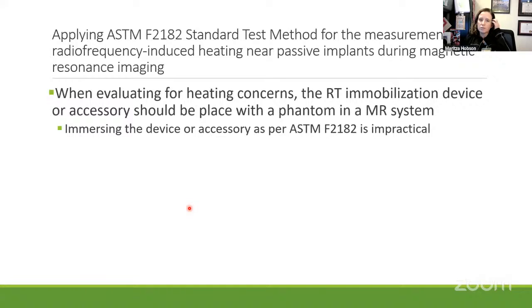Okay, so when we're applying ASTM F2182 for evaluating the heating concerns, the RT immobilization device or accessory should be placed with a phantom in an MR system. So why do we recommend a phantom? This is from our task group recommendation. It's because ASTM F2182 states that the RF heating test of passive implants requires that the devices be submerged in a test solution to mimic in vivo implantation.